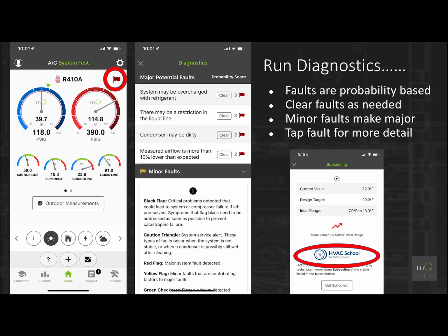But then as we get the charge corrected, all the other faults may completely clear out of the app, because a lot of them are interdependent. Now, the airflow being lower than expected is probably not going to correct itself, but in this case we're finding a charge and airflow problem. But remember, because there are so many similar faults, it'll always take a technician to figure out what's wrong with measureQuick.